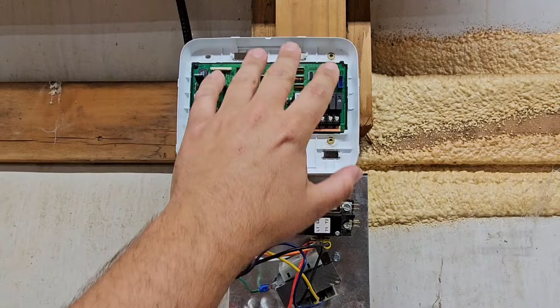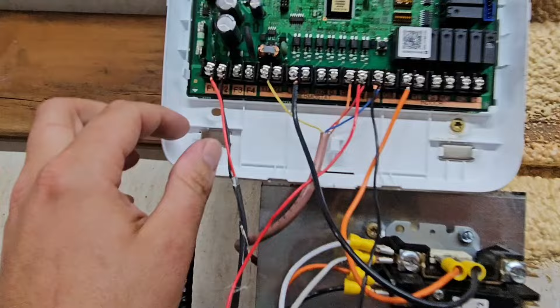So this is the AHU control. This is made by Samsung, and this is a control they use to be able to communicate with that outdoor unit and use that outdoor unit to make it compatible with a gas furnace, with a heat pump air handler, with a fan coil unit. So here's my communication wire. It comes into these terminals, F1 and F2. Then I've got a thermostat wire, so my thermostat can communicate to this board. And then I've got R and C, and my transformer is used to power this R and C to give the board 24 volts.